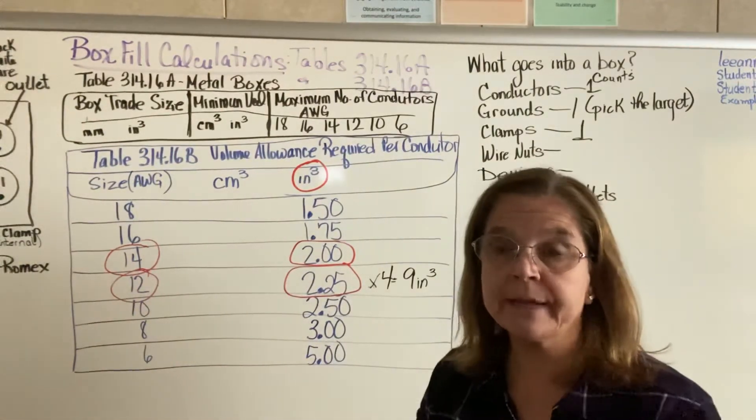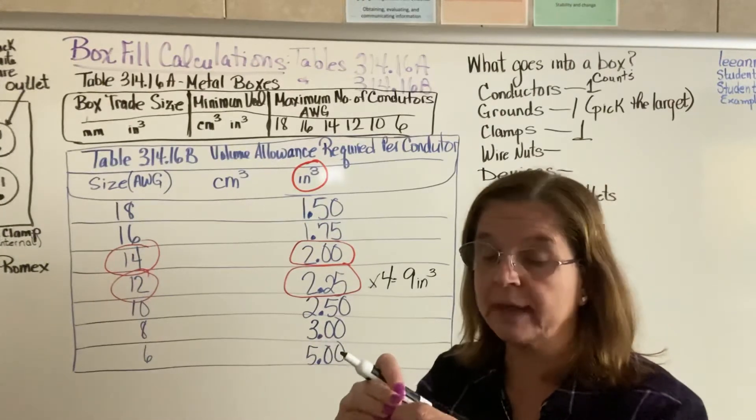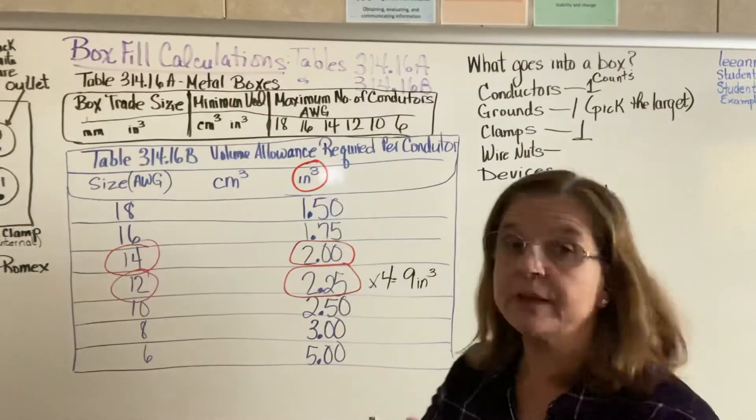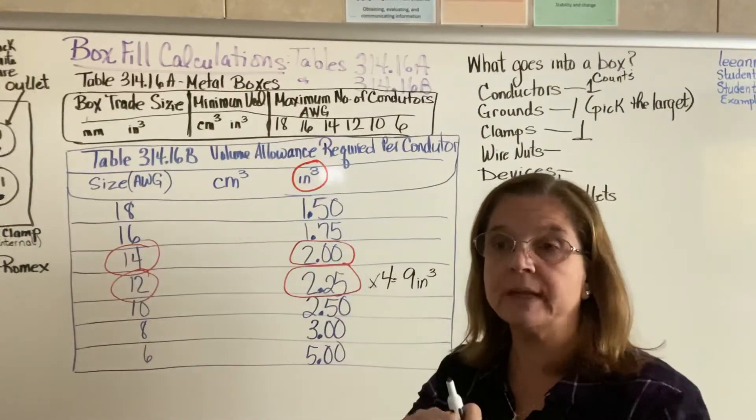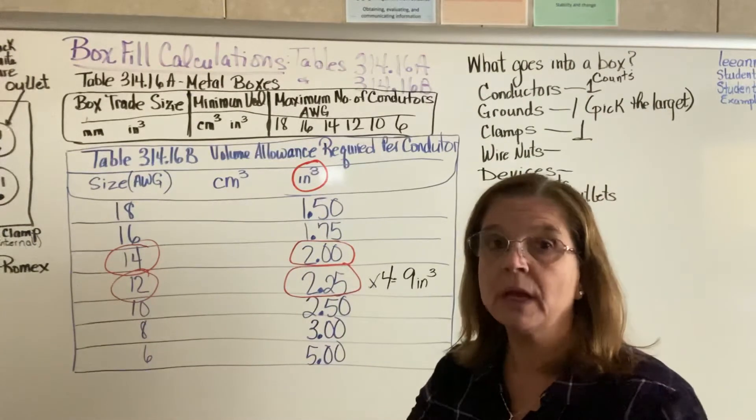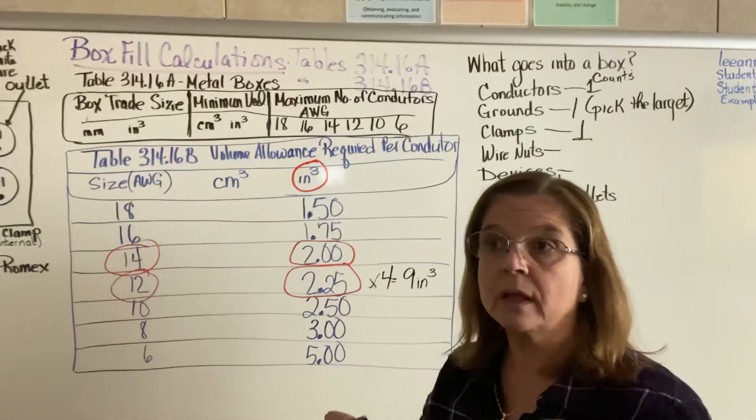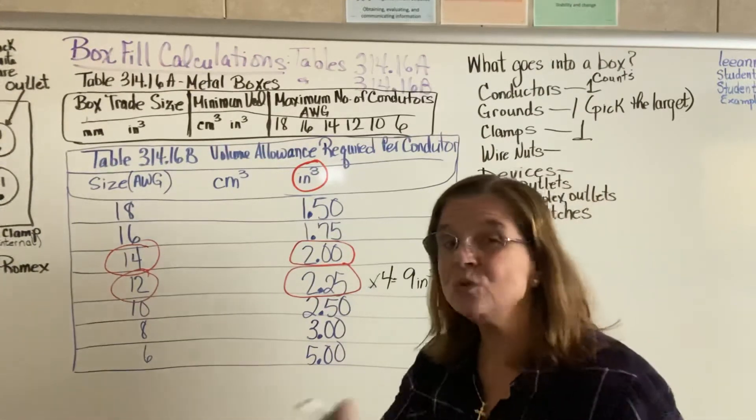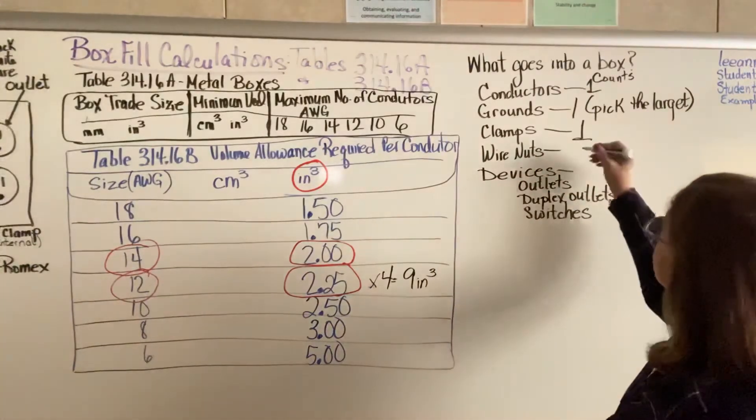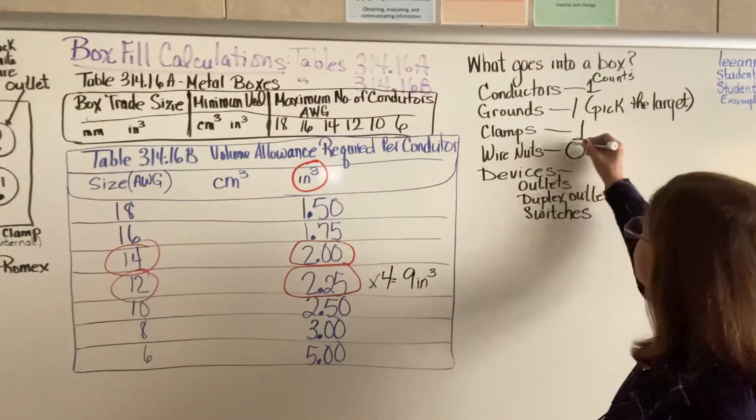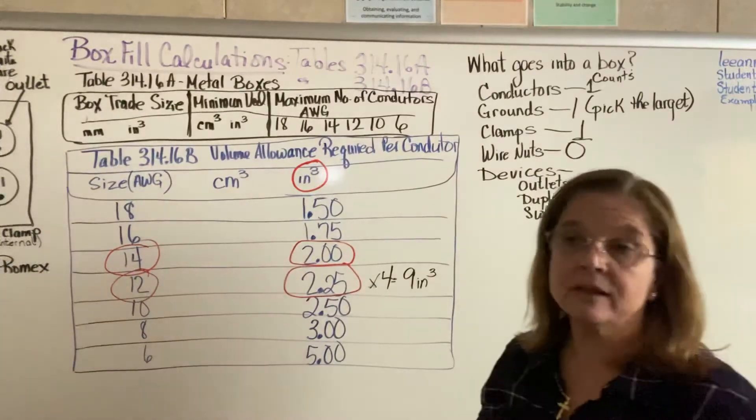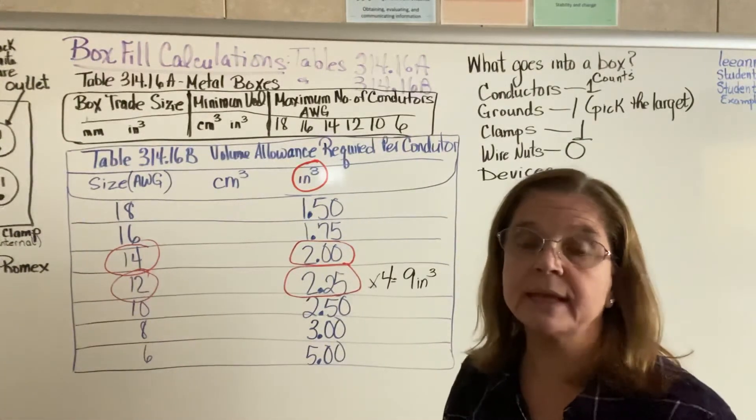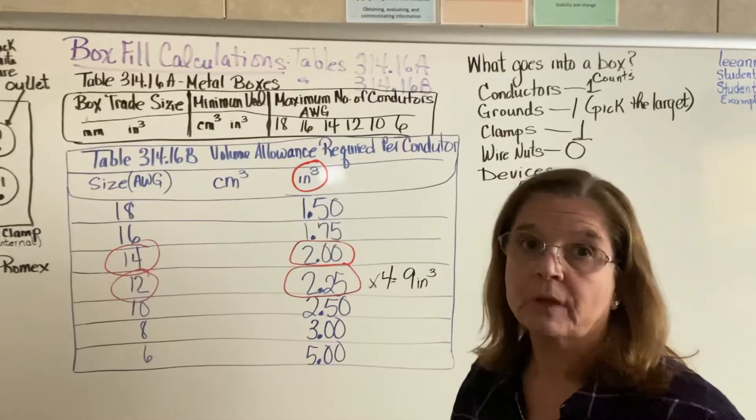If you use wire nuts to bring the three hot wires together and tighten them, and the three neutral to tighten them, and the three grounds to tighten them, if you're using any type of wire nut, they don't count at all. So wire nuts count zero. They're there just to hold the wires together and a pigtail for you.